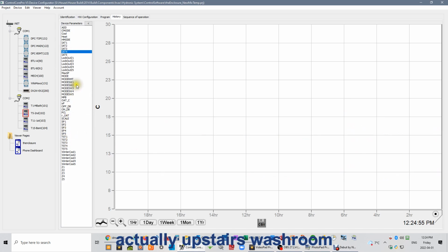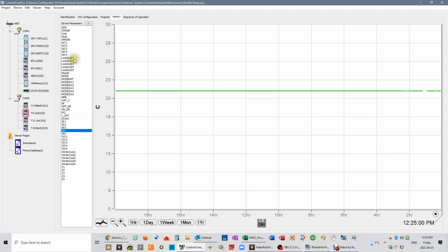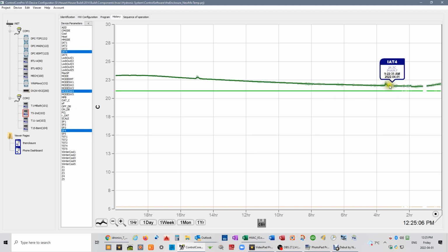This is the downstairs hallway. Whoops, sorry, wrong buttons here. And we can see set point. It's never reached the set point. It's always been above the set point. So the actuator has been off for the last 24 hours.